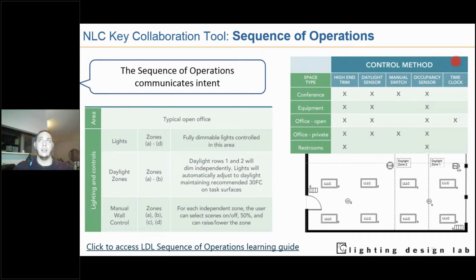So you can get a simpler sequence of operations at the beginning of your project, and it used to be like the quicker discussion piece, but then as the project progresses along, it is a good practice to have a more detailed sequence of operations. It does take a lot of time to generate, but it is very worth it when you're discussing the design intent of a project. LDL has developed a sequence of operations learning guide alongside a lot of guides. So if you can see the link below or go on our website for our resources, you can see our network lighting control series best practice guides.